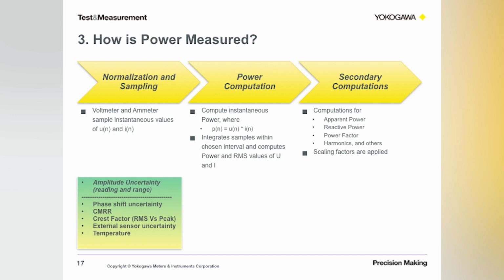Because the first two steps is where most of your error comes from in the form of amplitude uncertainty. This amplitude uncertainty can be caused due to internal phase shifts, burden losses, common mode rejection ratio, external sensor uncertainty, uncertainties due to your environment, temperature. Those are some of the factors that contribute towards the amplitude uncertainty. Then there are other uncertainties that come from period detection based on how clean your signals are and if certain filters need to be used to detect this measurement period. Remember, in power measurement, this period detection is one of the key things in measuring your good values for RMS and power, right?